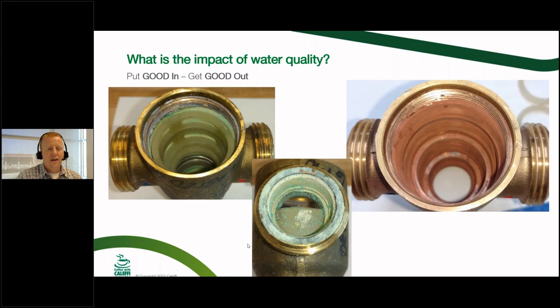And in this particular case, they told me that it lasted 6 months. I can't confirm or deny that. Okay, I can only go based on what they told me. They sent it back. They said, hey, it's not working. I opened this guy up. I said, well, what were you doing with this thing? And what they were actually doing with this thing is they had it on the outlet of a heat exchanger for domestic hot water. The other side of the heat exchanger was connected to a steam system, and that steam system was obviously very, very hot, and the water that was coming out of that heat exchanger was very, very hot, and it scaled. And it is what it is.